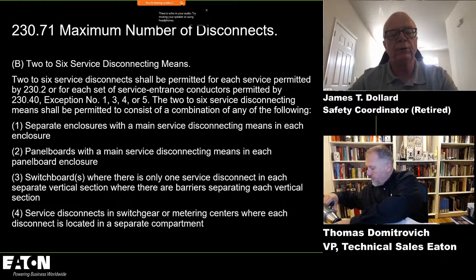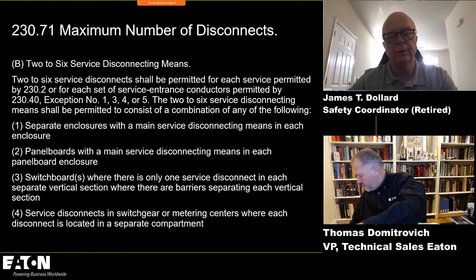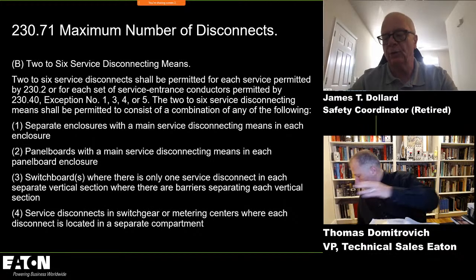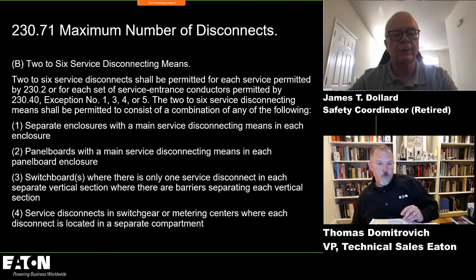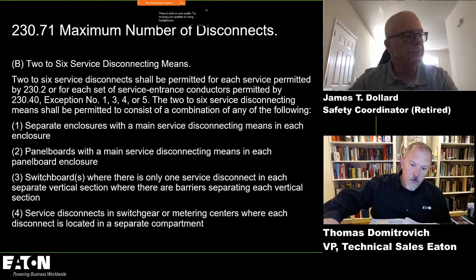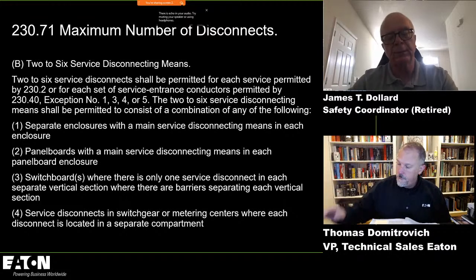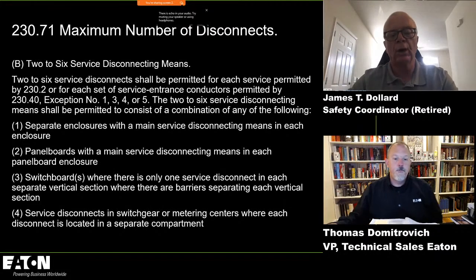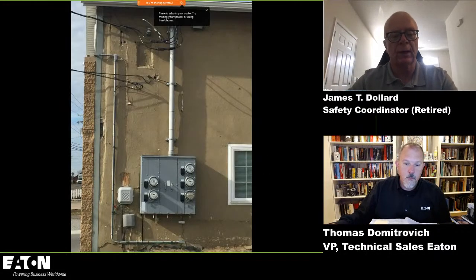But list item 2, we added panel boards with a main disconnect in each, because that was the most popular way of doing 6 disconnects. And then we got into switchboards where there's only 1 disconnect in each vertical section, and there's barriers. And 6 disconnects in switchgear is easy because it's compartmentalized. Metering centers, we're working on that. We've got some problems there.